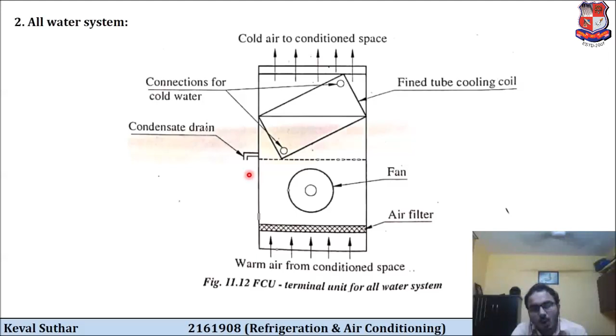This case is for summer air conditioning. Here we will be having inclined tubes of cold water, and the warm air will be passing from bottom to top through this cooling coil. This water will not come into contact with the warm air, as this is a form of indirect contact heat exchanger. The heat transfer can happen through conduction, convection and radiation, and then this cold air is again taken into the conditioned space, and here we are having a condensate drain. So this is all about the fan coil unit, which is the terminal unit for all water systems.